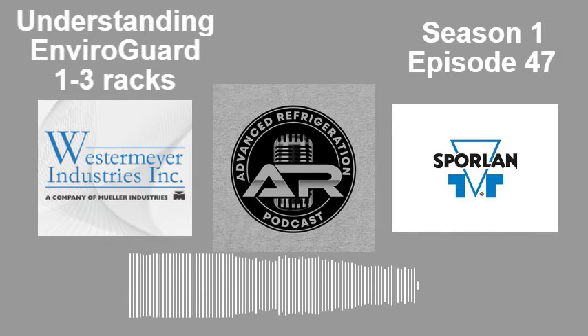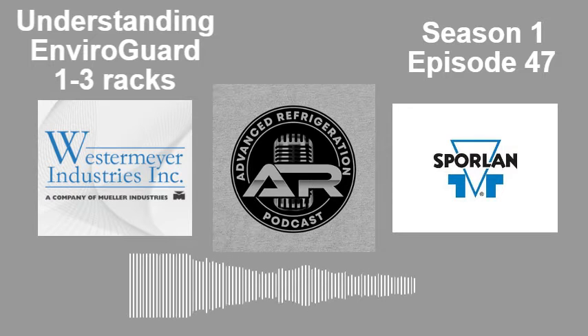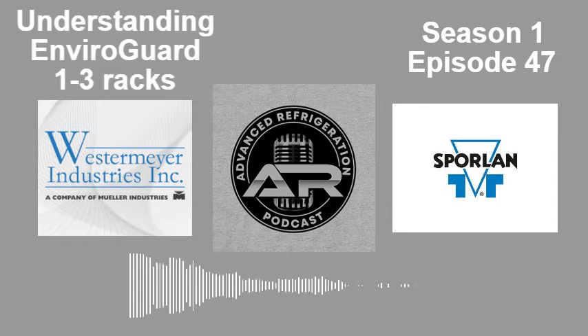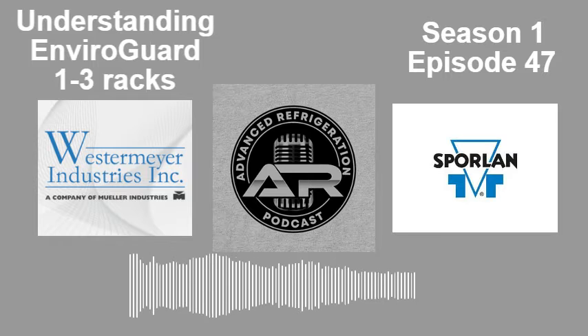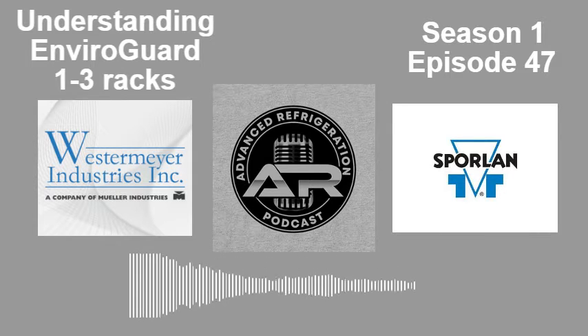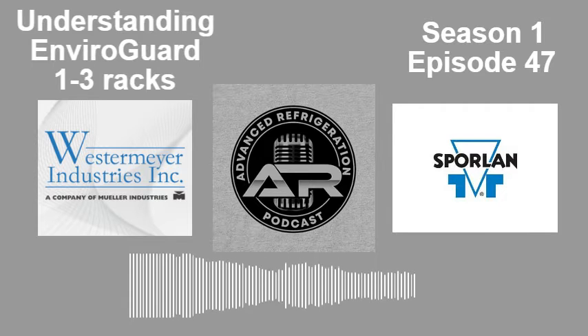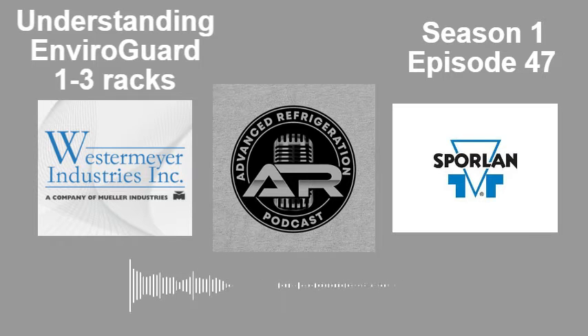Now we're going to transition into Enviro-Guard 2. So Enviro-Guard 2 came out to help with the issues with 1. So what Enviro-Guard 2 did is it started to introduce controls into this. CPC, Danfoss, Novar, Microthermal, whoever. So what Enviro-Guard 2 is, they put a normally open solenoid on, or sorry, normally closed solenoid, depending. Some of them were normally open, some were normally closed, in front of the SPR valve.